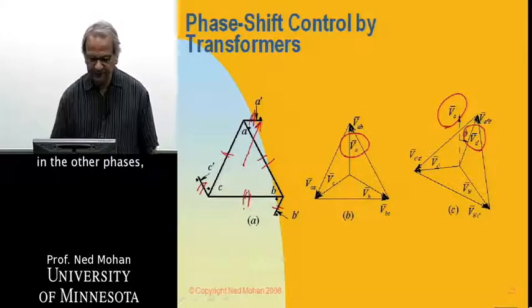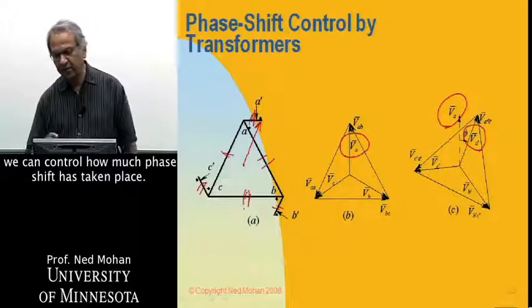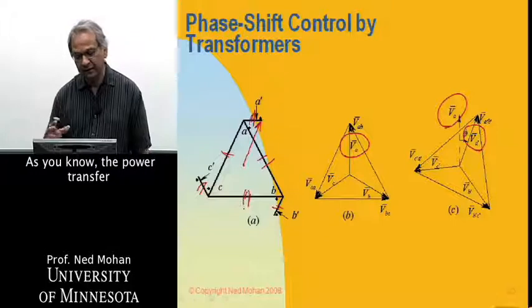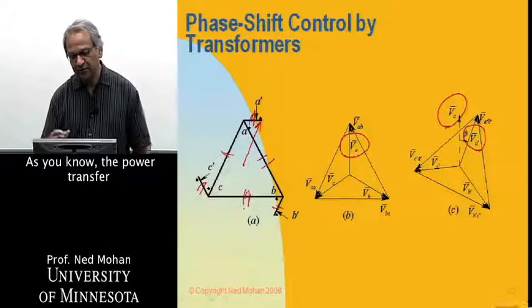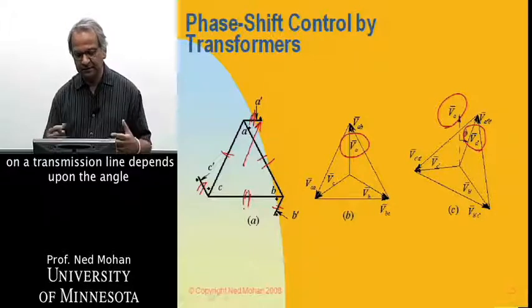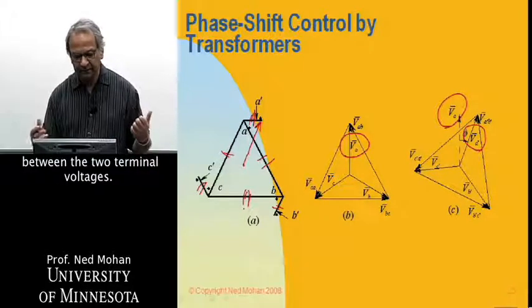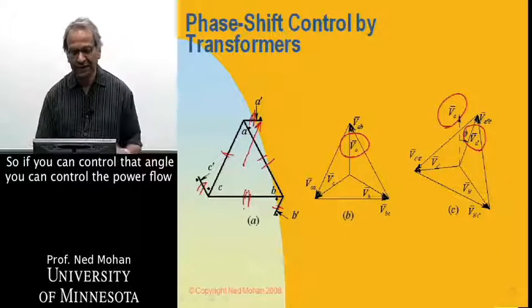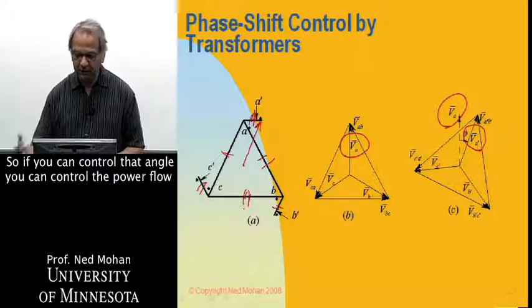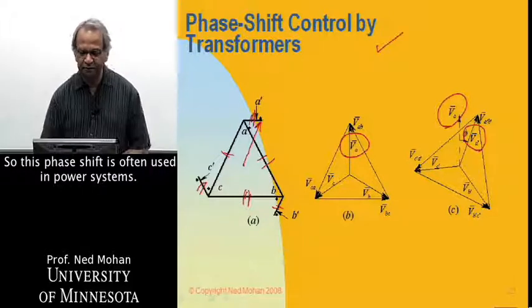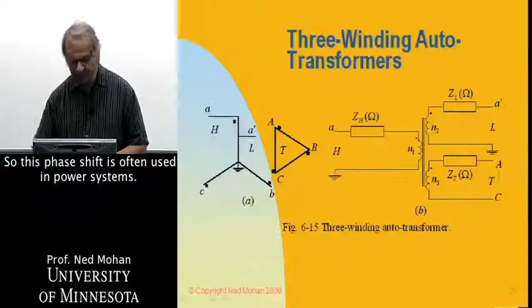So we can create this phase shift, and depending upon the number of turns between this winding and this winding, and similarly in the other phases, we can control how much phase shift is taking place. And as you know, the power transfer on a transmission line depends upon the angle between the two terminal voltages. So if we can control that angle, we can control the power flow on a given transmission line. So this phase shift is often used in power systems.